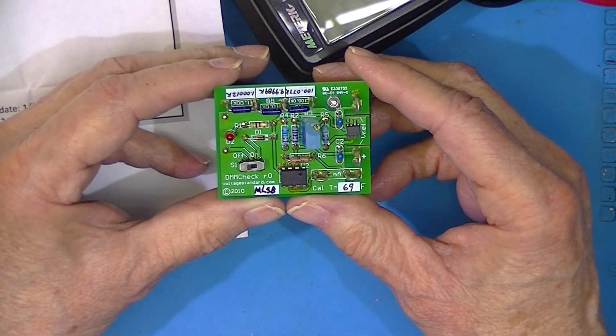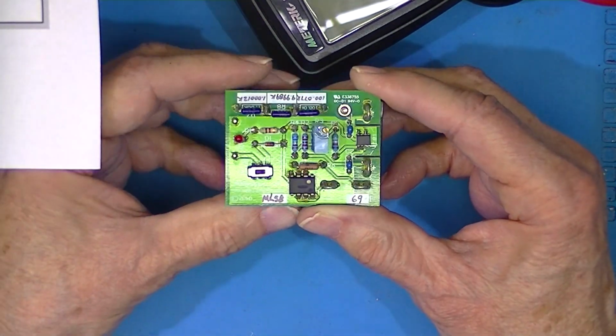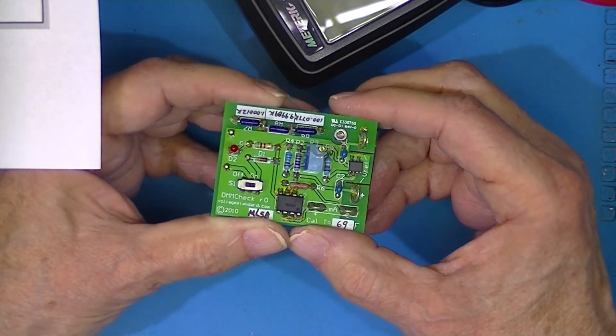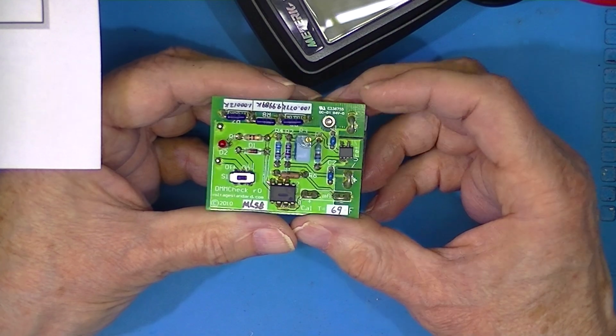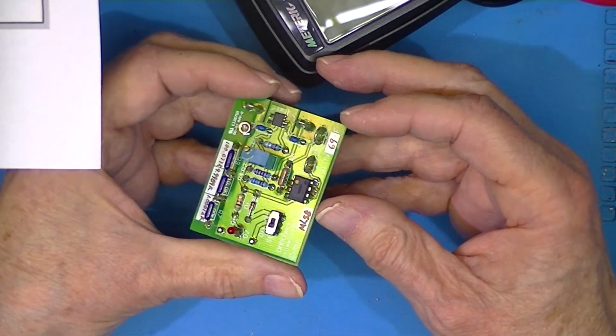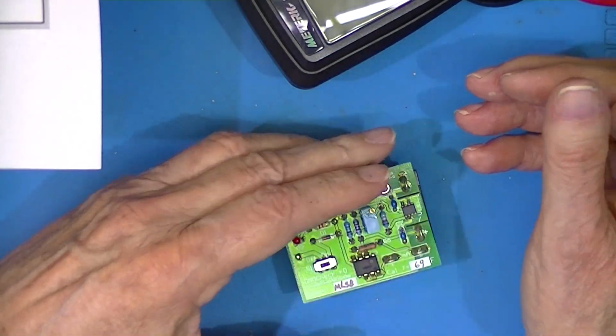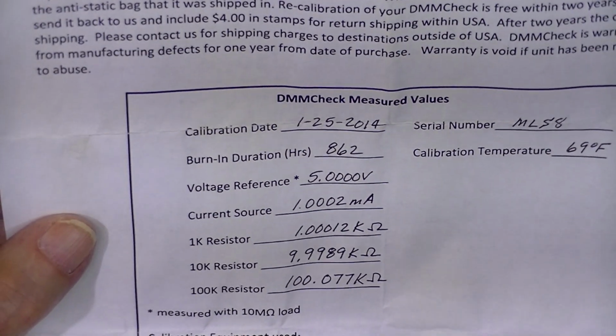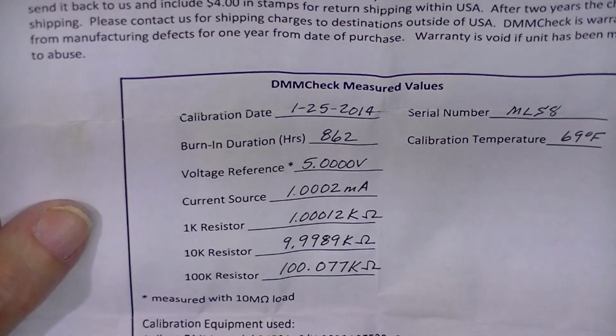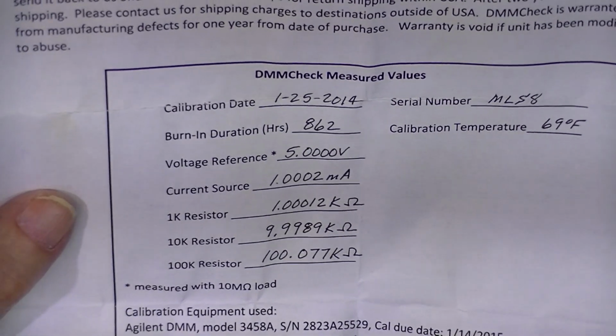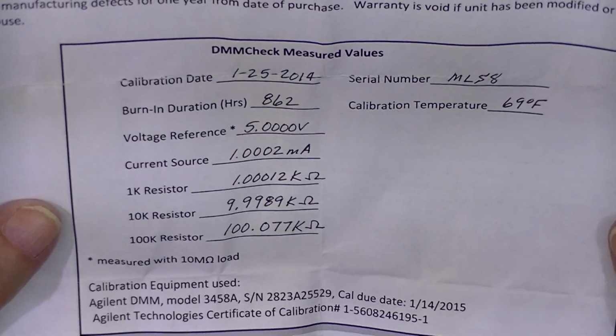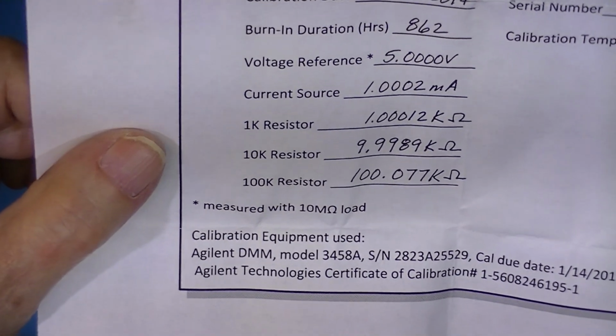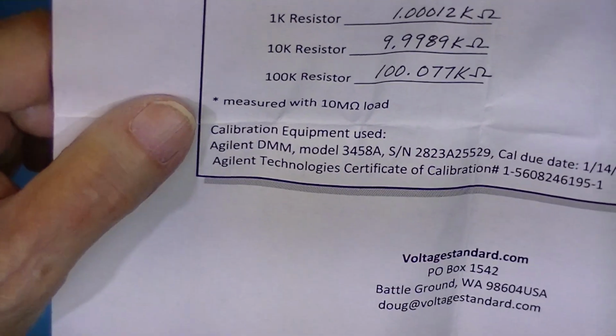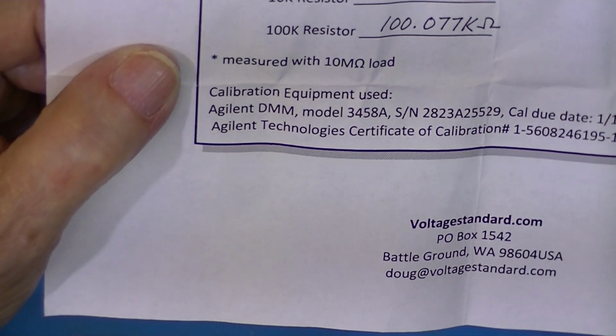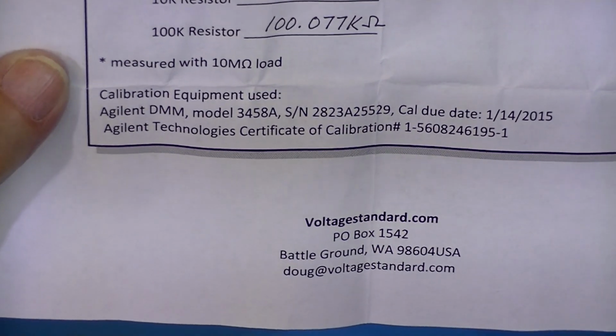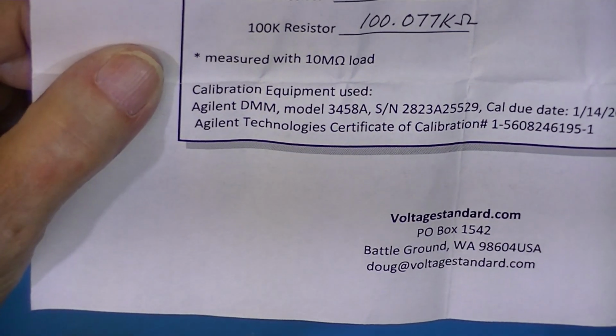Now, they don't make this version anymore. When I bought this, it wasn't very expensive. It provides 3 different resistance standards, a voltage reference, and a current reference. And what I consider to be a real calibration certificate. It has a date. It has a serial number. It actually has a calibration temperature, which it should. And then these are the measured values. And they give you not only the model of the calibration device, the due date, and the serial number of the Agilent device.